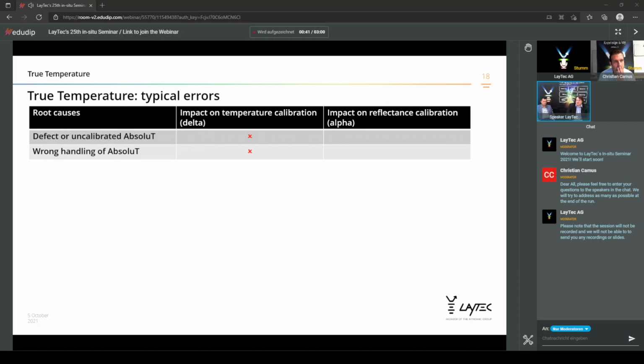This can lead to the emission being reflected or clipped by a sidewall or an edge of the optical channel of the viewport of the aperture, and then again lead to a wrong delta calibration, because the amount of light reaching the detector for that particular temperature on 950 nanometers or 405 nanometers in terms of the Pyro 400 does not correspond to the expected reference value.